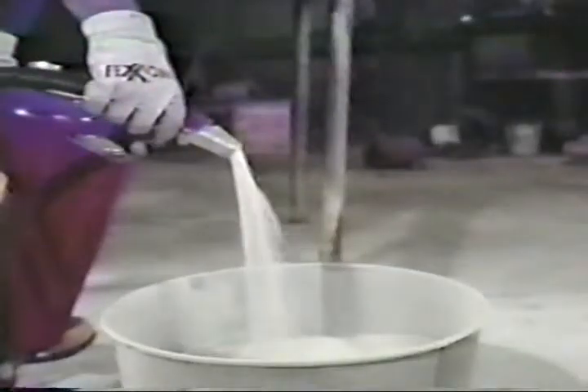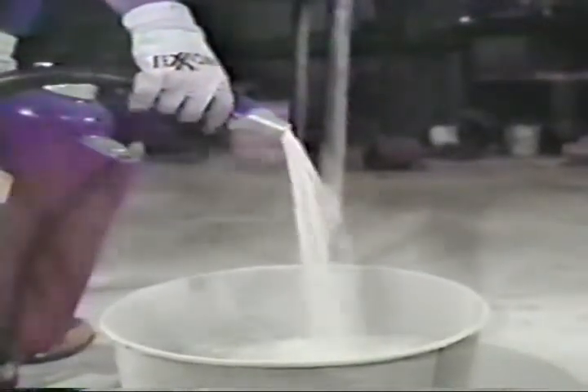Discharge the extinguisher from its maximum range of 6 to 8 feet. When control is established, ease back on the nozzle to produce a soft, heavy flow, which allows you to get close without scattering the burning metal. If hot spots appear on the surface, continue to apply the agent. Remember, the metal remains quite hot for some time.